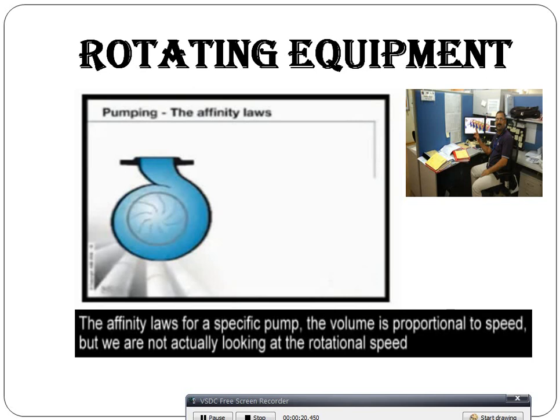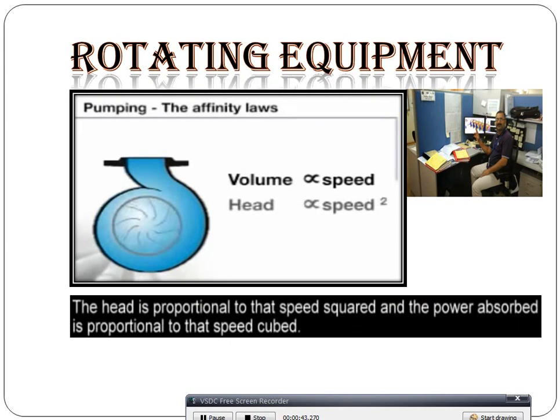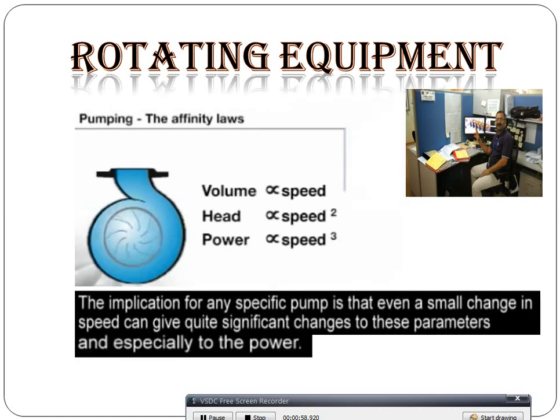Keep in mind the affinity laws for a specific pump, but the volume is proportional to speed. We are not actually looking at the rotational speed; we are looking at the peripheral speed of the head. The head is proportional to that speed squared, and the power of your pump is proportional to that speed cubed. The implication for a specific pump is that even a small change in speed can give quite a significant change to this parameter, and especially to the power.